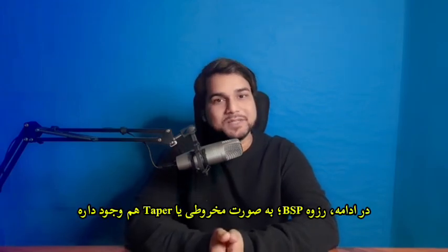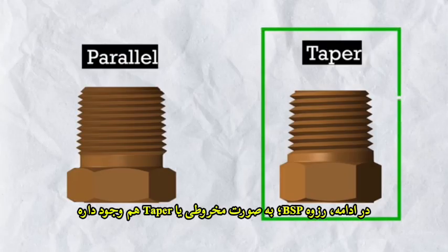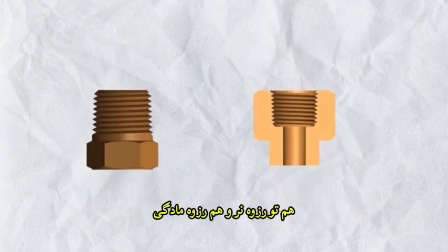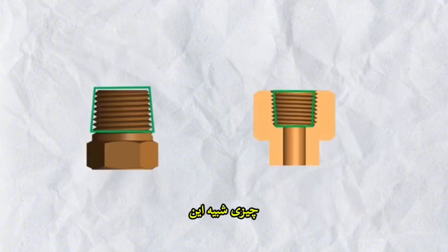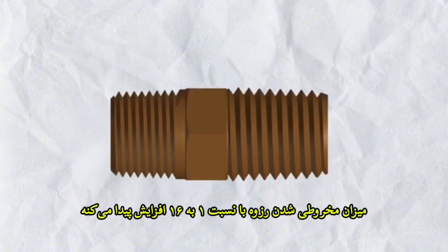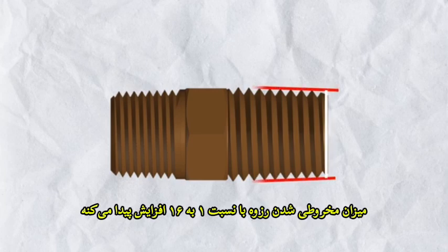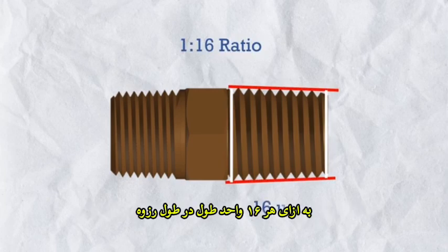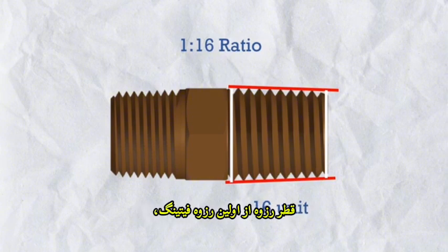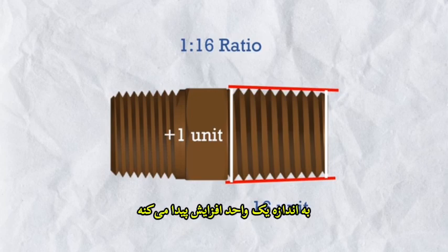And now the BSP thread also comes in taper shape in both male and female thread. Something like this. The thread taper increases by a 1/16 ratio. Means at every 16 units of measurement along the thread length, the thread diameter will increase by 1 unit from the starting thread.